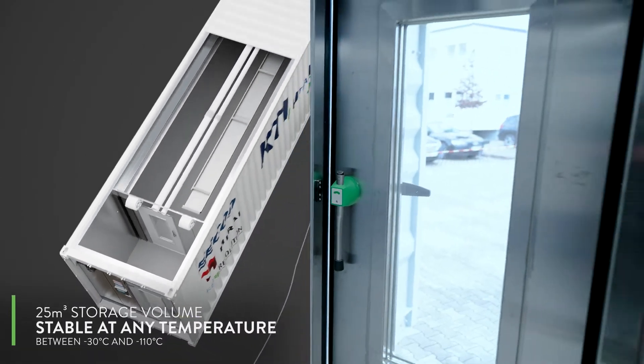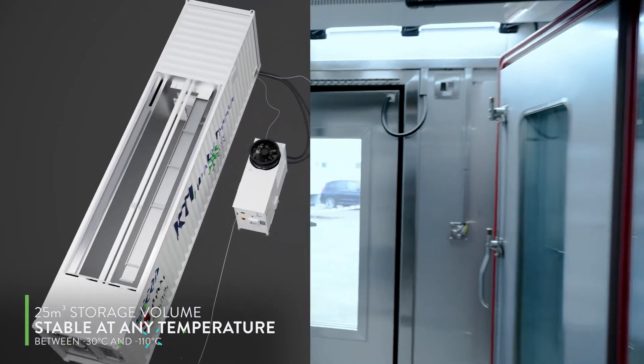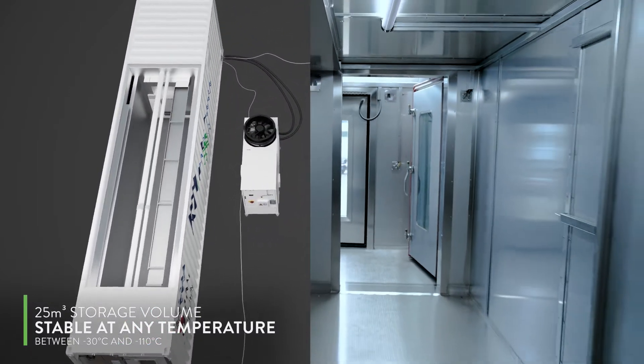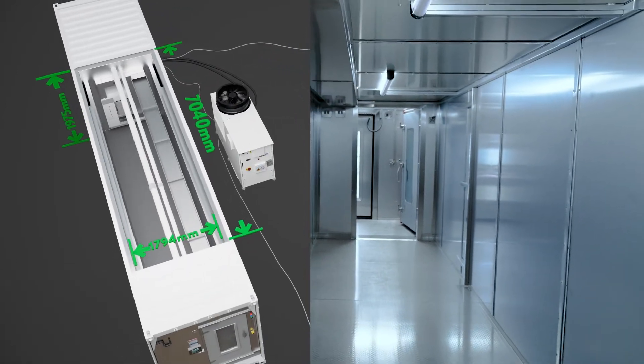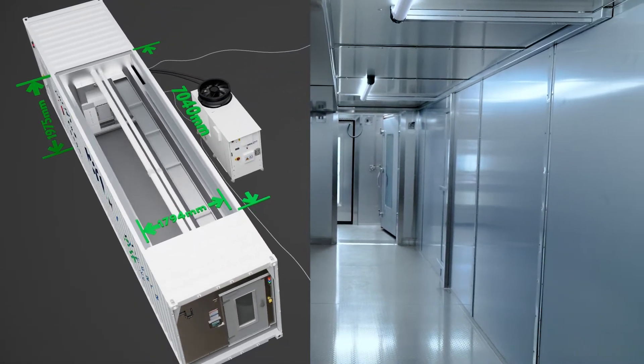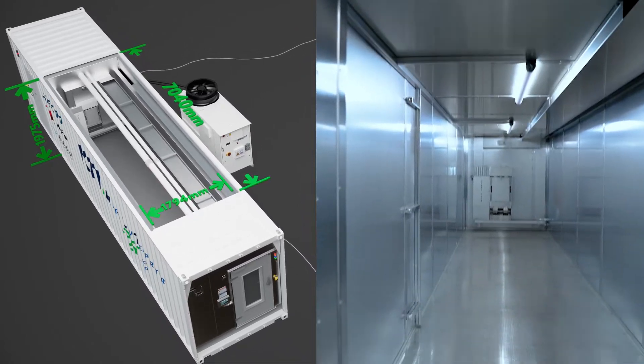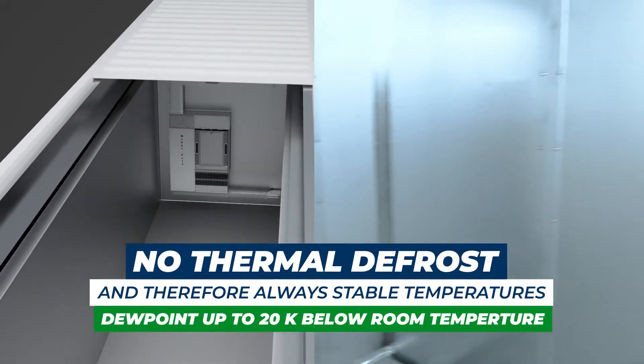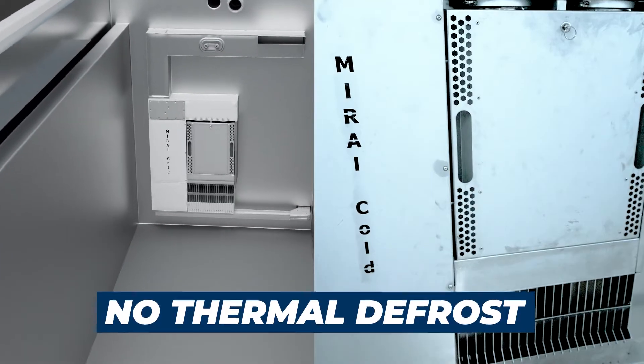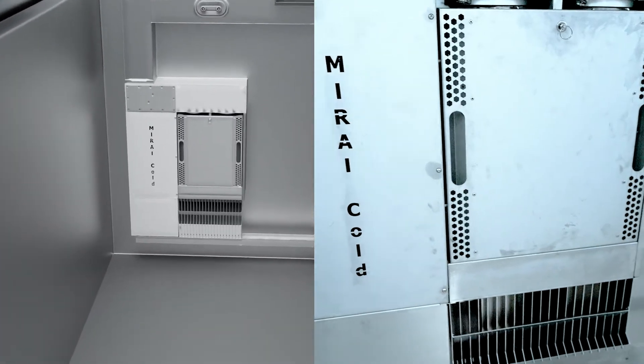The main storage room has a total use volume of 25 cubic meters that can flexibly be controlled at any temperature between minus 30 and minus 110 degrees Celsius with just the push of a button. The mechanical de-icing system by Mirai Cold results in dry air and stable temperature distribution at any time, without inefficient thermal defrost.